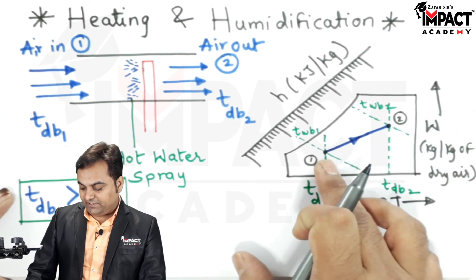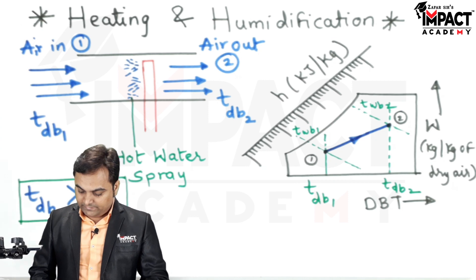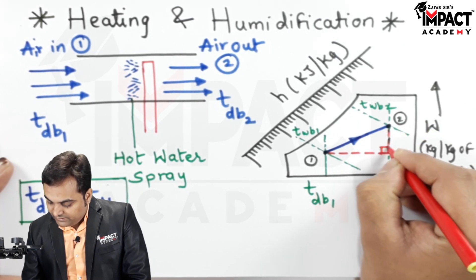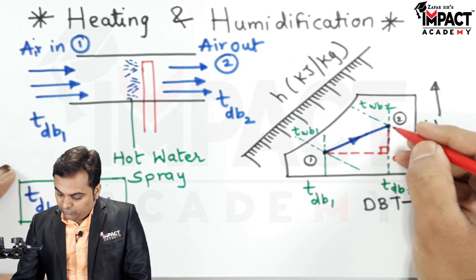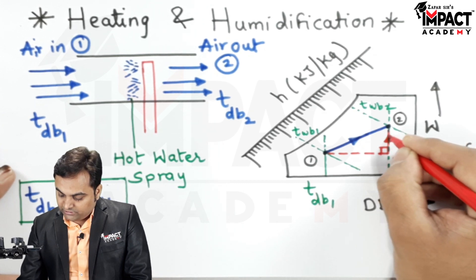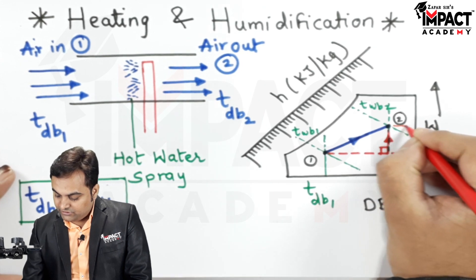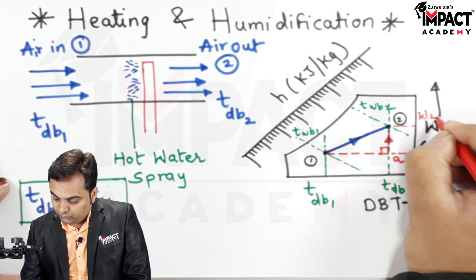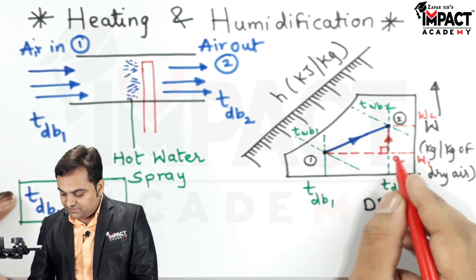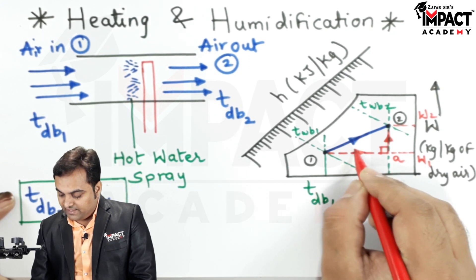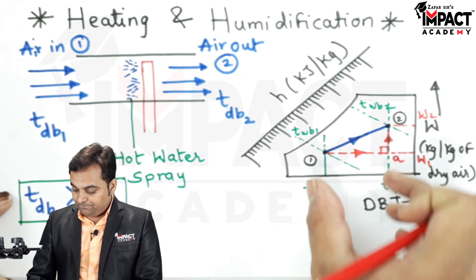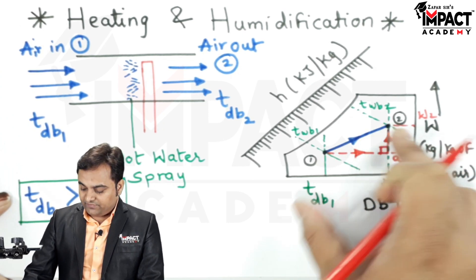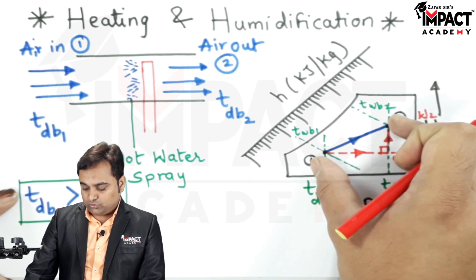Joining points 1 and 2 gives us the process line, which represents heating and humidification. From point 1, I draw a horizontal line and from point 2 a vertical line; their intersection is point 'a'. From 1 to a the moisture content remains the same at w1 while temperature increases from tdb1 to tdb2 — this is sensible heating. From a to 2 the temperature is constant while moisture increases from w1 to w2 — this is humidification. The resultant line 1 to 2 shows the combined effect.